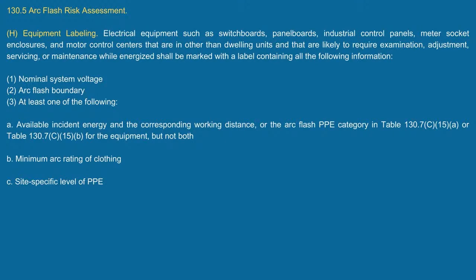Now, you're going to see in 110.16 of the National Electrical Code pretty much identical, word for word, the very first part of this. Electrical equipment, such as switchboards, panel boards, industrial control panels, meter socket enclosures, and motor control centers that are in other than dwelling units and that are likely to require what? Examination, adjustment, service, or maintenance while energized shall be marked with a label containing the following information. Now, when you go look at 110.16, it says you have to identify that an arc flash hazard is present, right? Yeah, yeah. Okay, that's the difference.